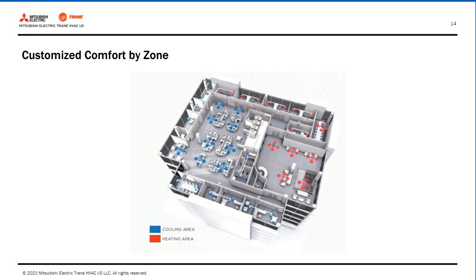Everyone always, in different spaces that are even sometimes next to each other, prefers different set points. The zoning also allows for temperatures of different spaces within a building that's entirely in one mode to be set a couple of degrees higher or lower to match the comfort level of the people in the space. In crowded spaces, for instance, where more body heat is being emitted, occupants may appreciate the air to be slightly cooler than in a more open area with fewer people. This is particularly beneficial for mixed-use applications where one building can serve multiple purposes. With so many spaces with unique functions and occupancies, having the ability to customize conditioning for each individual zone can make all the difference.